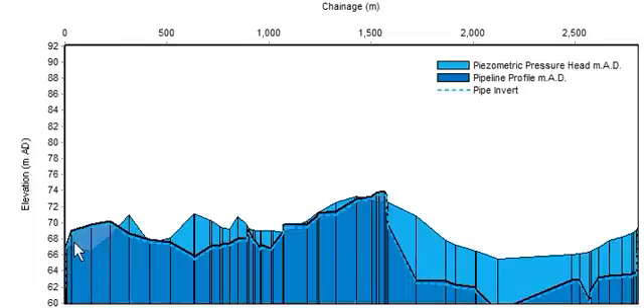If vapor cavities form, when the pressures normalize these cavities collapse very rapidly, causing very high pressures close to the pipe wall. This can damage the pipe wall over time or instantaneously cause a catastrophic failure.